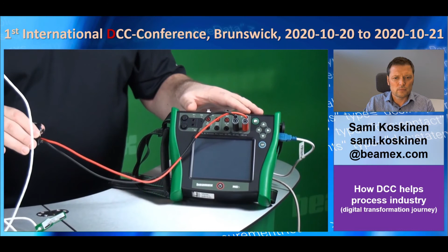We'll start off with our temperature element that we're plugging into our temperature source. That connects to our temperature transmitter. The transmitter converts this temperature into a milliamp output. The calibrator then measures that milliamp output, and at the same time we can provide a 24-volt loop power back to power up the transmitter. The dry block itself tells us what temperature that it's at.